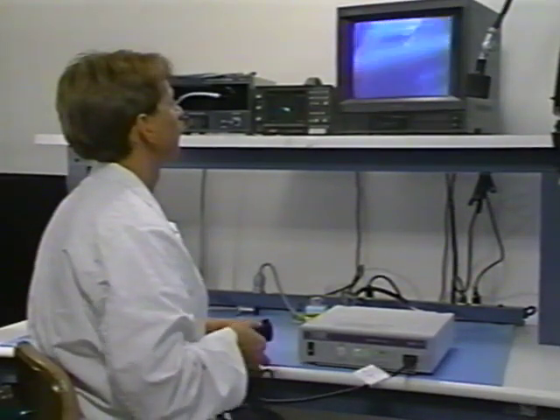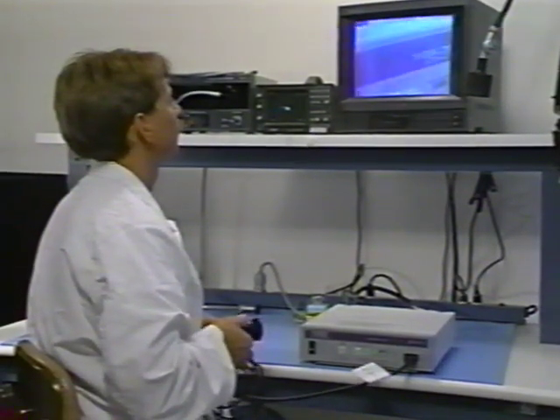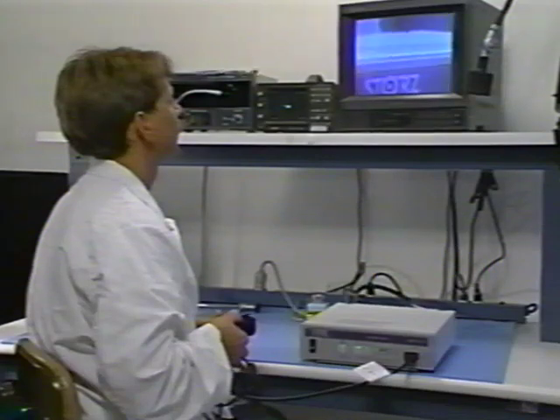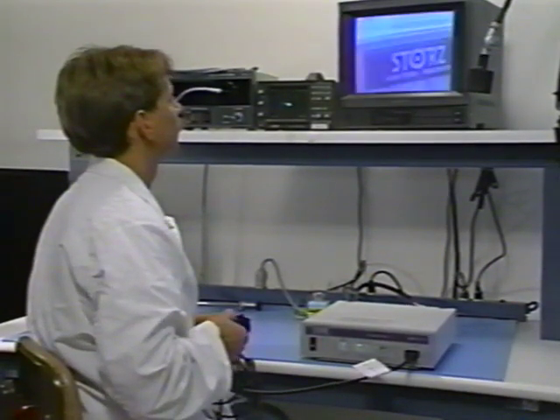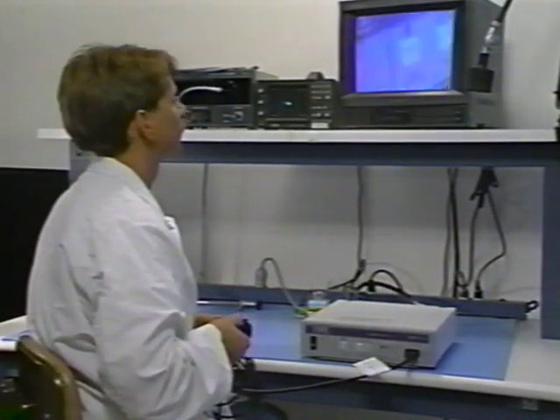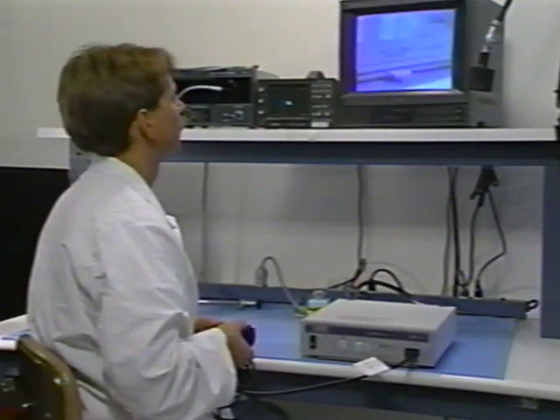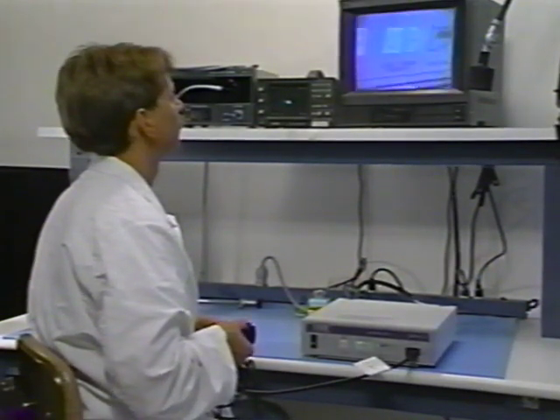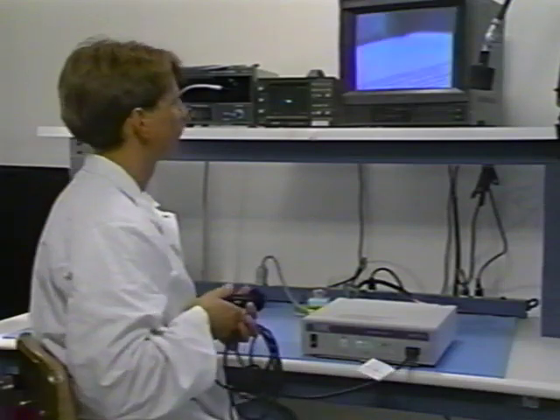You will save valuable downtime if you can resolve some of the smaller issues without sending the camera out for repair. Problems that do require opening the camera head or CCU will still need to be handled by an authorized repair service. Do not open the camera head or CCU. This will void the warranty and may introduce contaminants into the optical system.